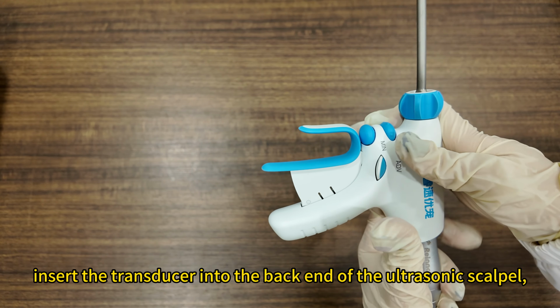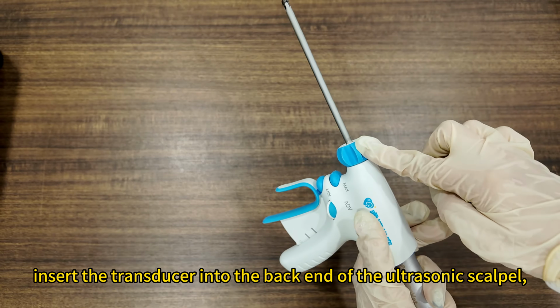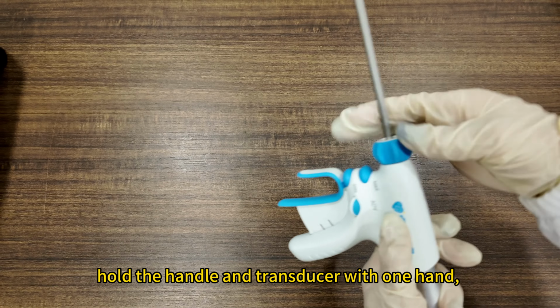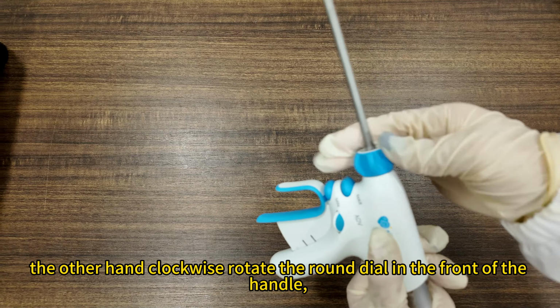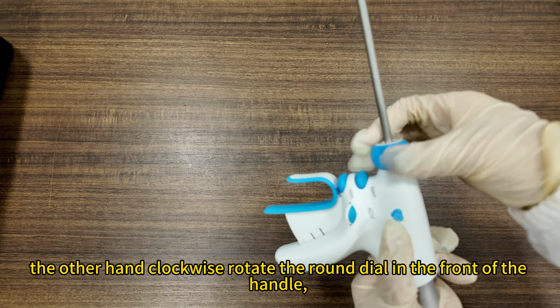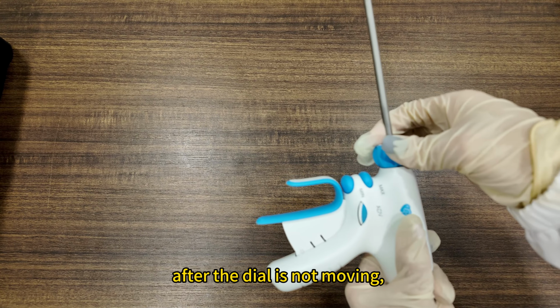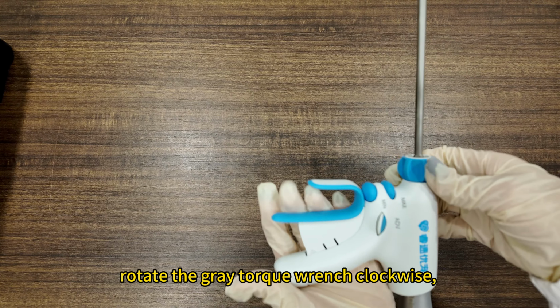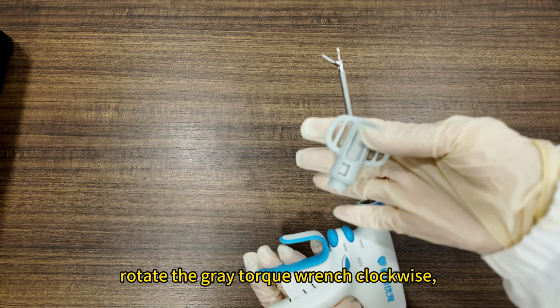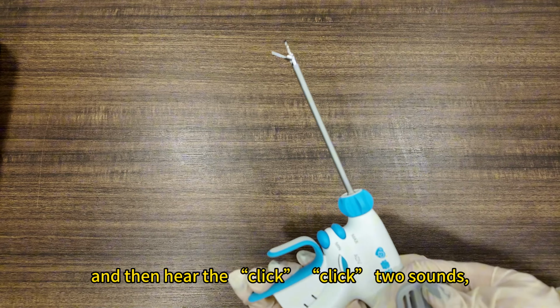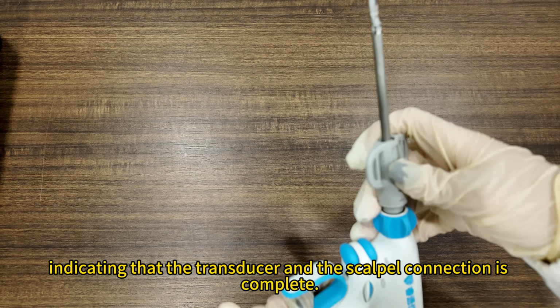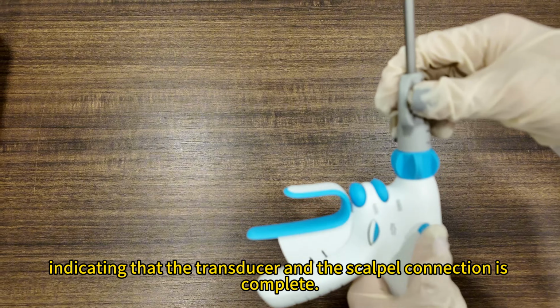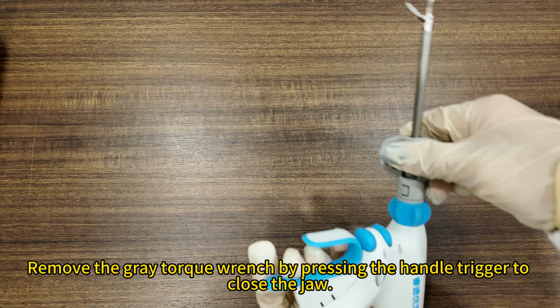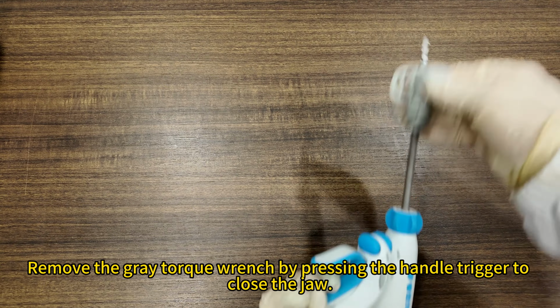Insert the transducer into the back end of the ultrasonic scalpel. Hold the handle and transducer with one hand. With the other hand, rotate the round dial in the front of the handle clockwise. After the dial is not moving, rotate the gray torque wrench clockwise, and when you hear the click-click sounds, it indicates that the transducer and the scalpel connection is complete. Remove the gray torque wrench by pressing the handle trigger to close the jaw.